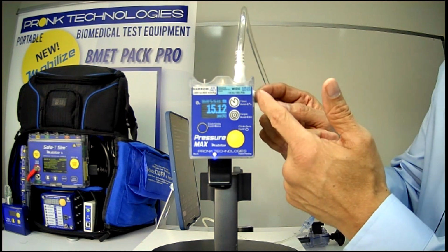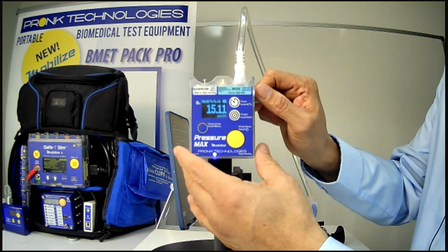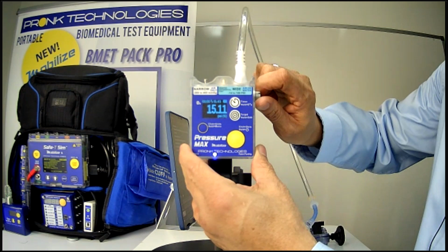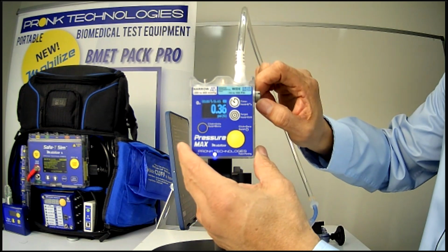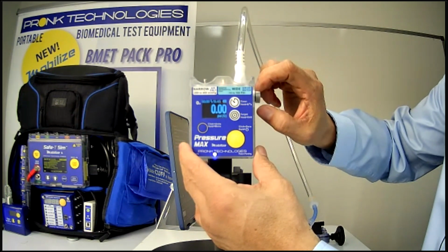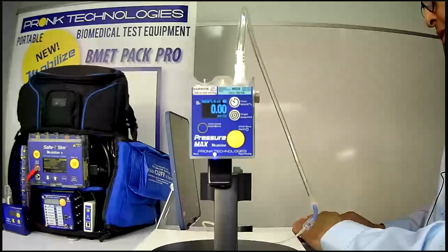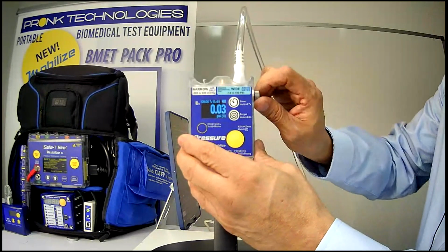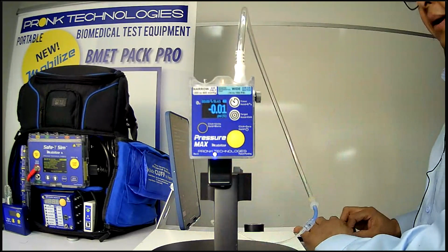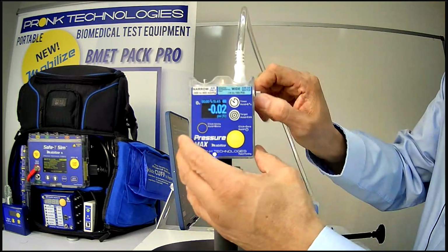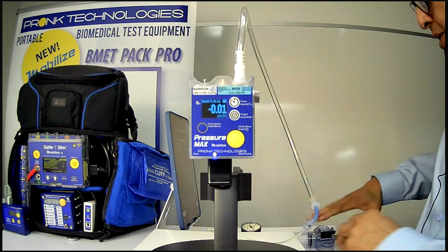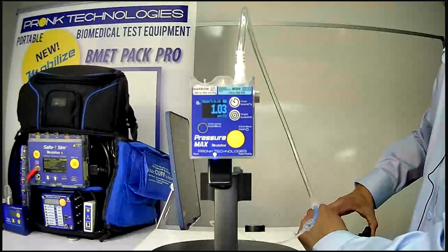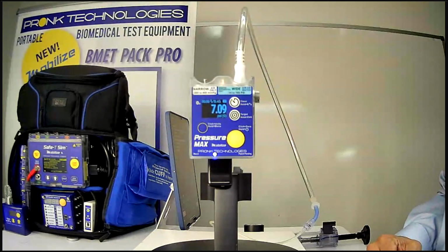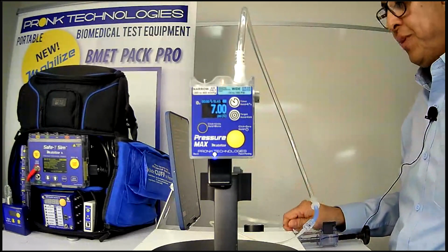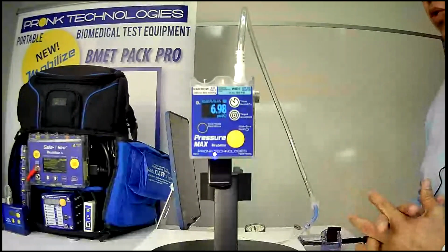And if I ever needed to bleed the fluid out of there, or you want to bleed the air down, no need to disconnect. You could just bleed it from here and use it to tune the pressure if you wanted to, or just reset it back to atmospheric. And then you can pressurize it again to do that. So I can open it back up. I'll open it back up. I'll go ahead and close it again, and then I can repressurize the system and take another measurement. So it really is useful and makes it easy to make those pressure measurements, having that thumb screw there to do the bleeding to make sure that you're within the range that you want to be within.